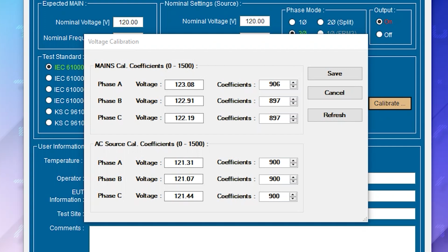We have the mains calibration coefficient on the top and the AC source calibration coefficients on the bottom. For each of the mains input phases, we need to measure the line to neutral voltage using a digital multimeter. With that value, we'll adjust the mains calibration coefficient for each phase to match the displayed voltage on our DMM.